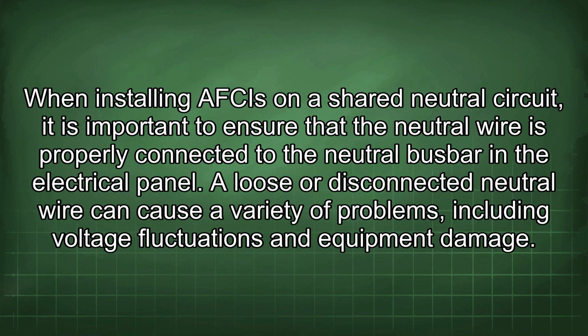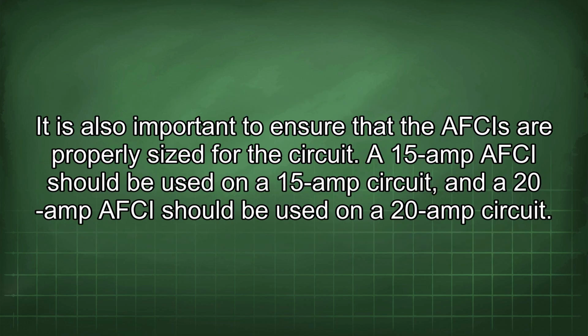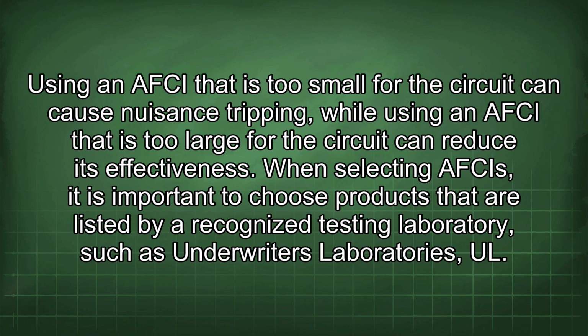When installing AFCIs on a shared neutral circuit, it is important to ensure that the neutral wire is properly connected to the neutral busbar in the electrical panel. A loose or disconnected neutral wire can cause a variety of problems, including voltage fluctuations and equipment damage. It is also important to ensure that the AFCIs are properly sized for the circuit. A 15-amp AFCI should be used on a 15-amp circuit, and a 20-amp AFCI should be used on a 20-amp circuit. Using an AFCI that is too small for the circuit can cause nuisance tripping, while using an AFCI that is too large for the circuit can reduce its effectiveness.